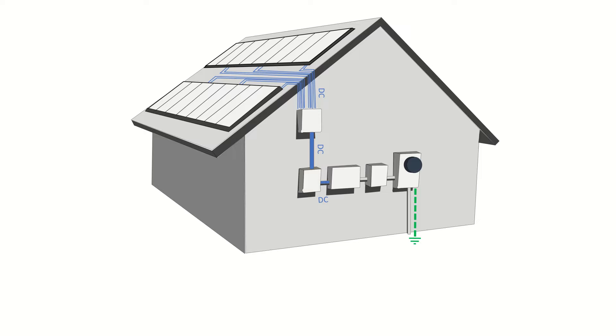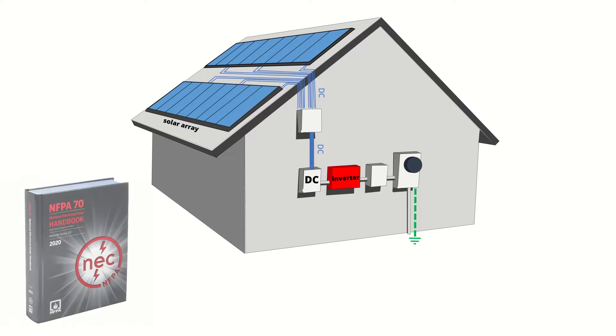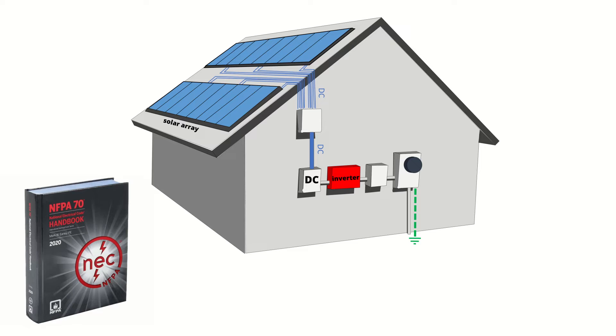In a solar electric system, the DC disconnect, often called a PV disconnect, will be placed between the solar array and the power inverter so that it can easily be thrown if you or the fire department needs to shut off the power coming from the solar array. Safety switches like this are a necessity in most residential and commercial applications in accordance with the National Electric Code or NEC.